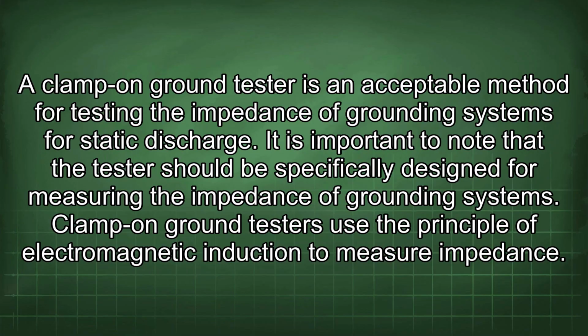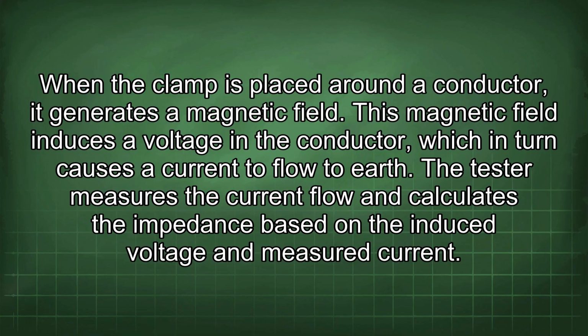Clamp-on ground tester is an acceptable method for testing the impedance of grounding systems for static discharge. It is important to note that the tester should be specifically designed for measuring the impedance of grounding systems. Clamp-on ground testers use the principle of electromagnetic induction to measure impedance. When the clamp is placed around a conductor, it generates a magnetic field. This magnetic field induces a voltage in the conductor, which in turn causes a current to flow to Earth. The tester measures the current flow and calculates the impedance based on the induced voltage and measured current.